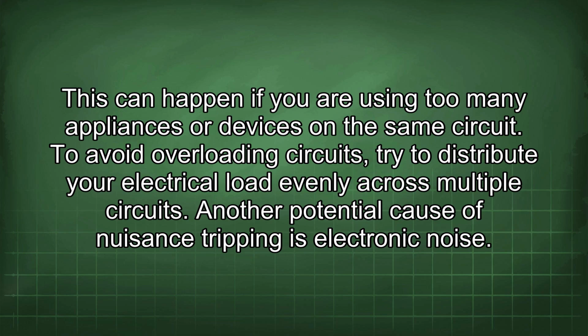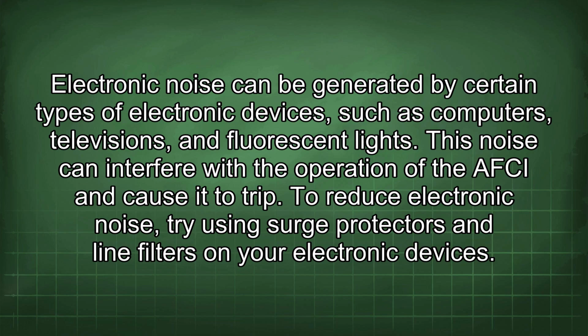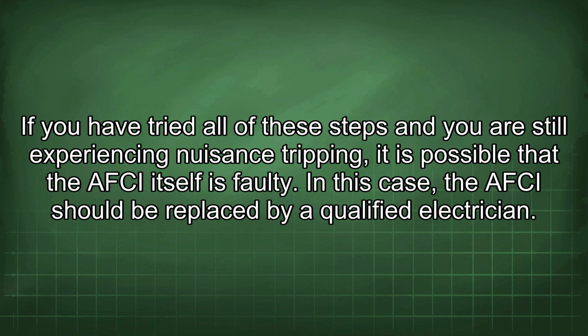Another potential cause of nuisance tripping is electronic noise. Electronic noise can be generated by certain types of electronic devices, such as computers, televisions, and fluorescent lights. This noise can interfere with the operation of the AFCI and cause it to trip. To reduce electronic noise, try using surge protectors and line filters on your electronic devices. If you have tried all of these steps and you are still experiencing nuisance tripping, it is possible that the AFCI itself is faulty. In this case, the AFCI should be replaced by a qualified electrician.